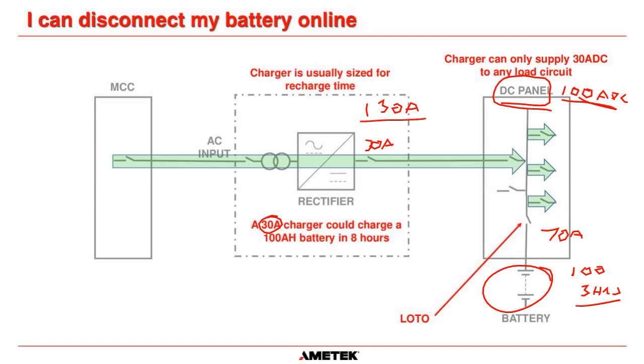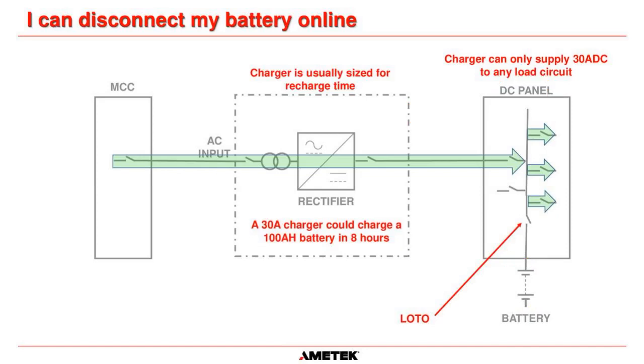A good design engineer will factor that into the system to allow the DC panel to accept 100 amps and have the 30 amps spare to charge the batteries. That's a good design engineer. Unfortunately, 20 years in the business has shown that that has not been the case. So good spotting, John. I like to be kept on my toes.